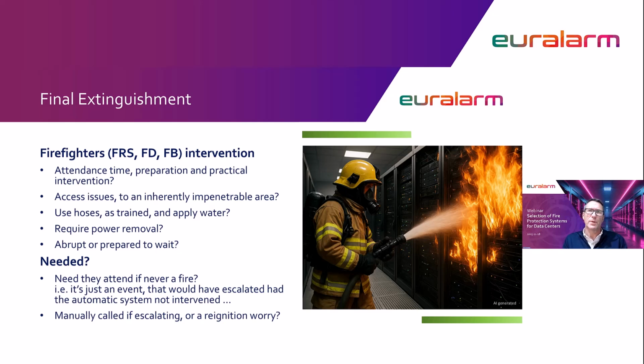Let's think about that for a moment. If you have a rack of cabinets, one of which is on fire, to a sprinkler system, that rack may as well be an umbrella. Water mist might fare better in suppression, but both are unlikely to fully extinguish.